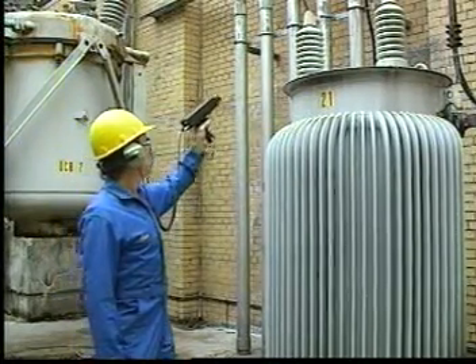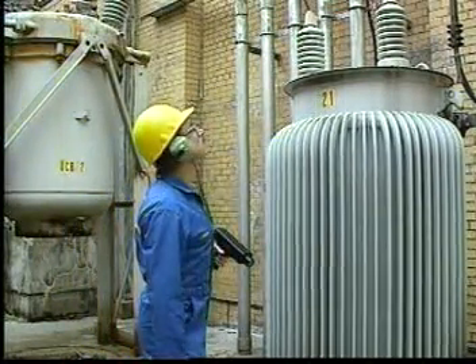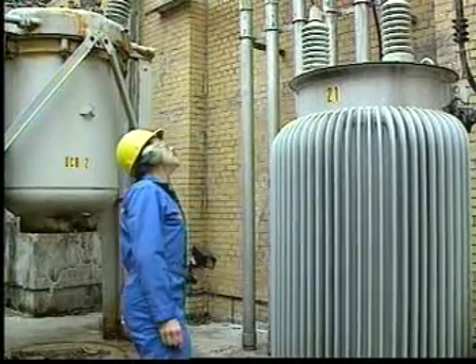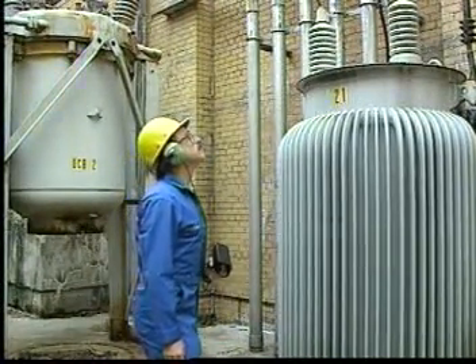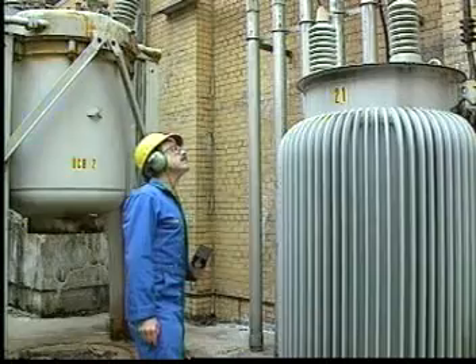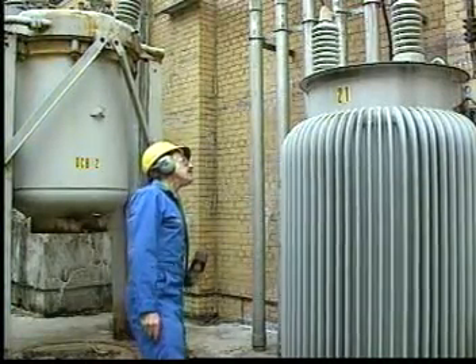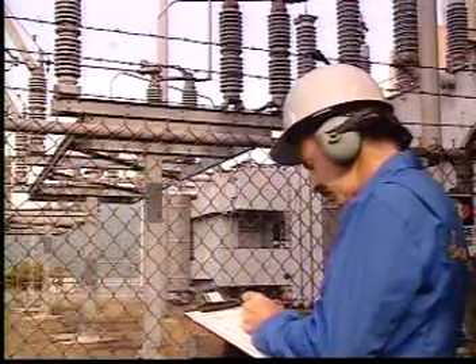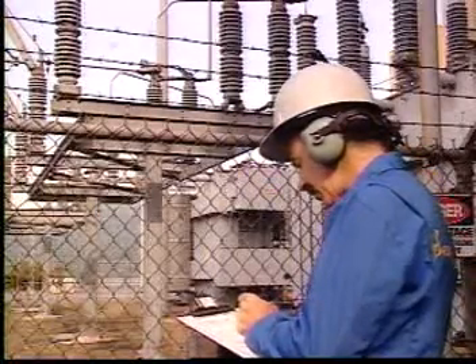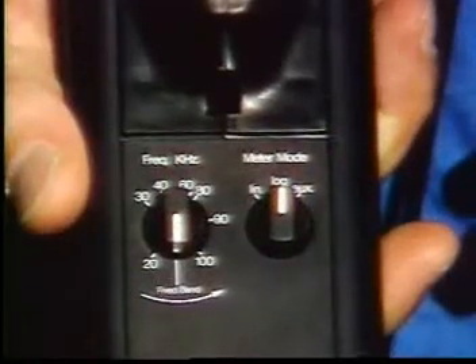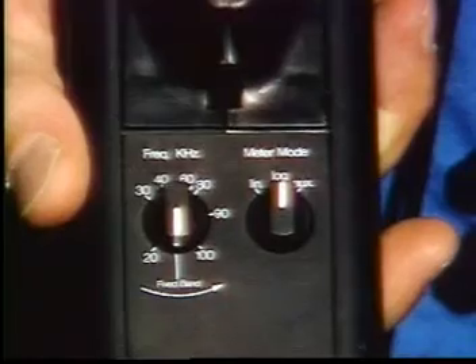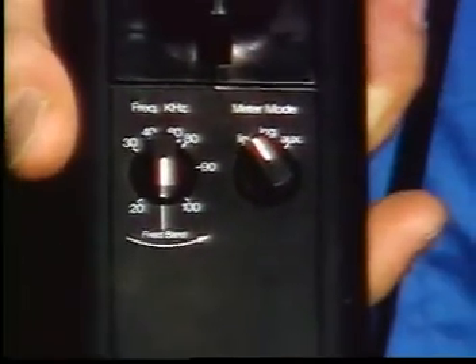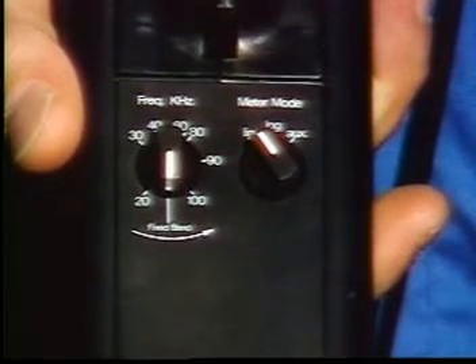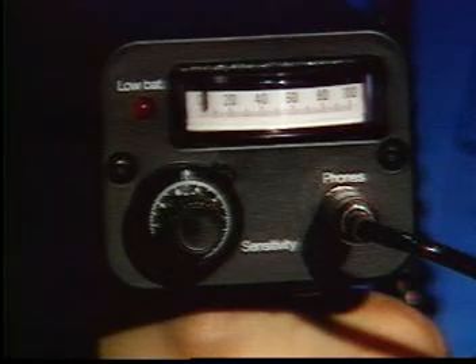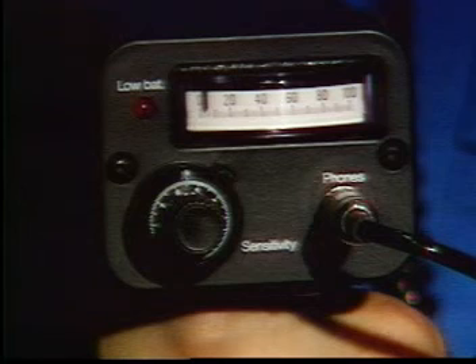Just as you may use complementary technologies, you may use your own senses to detect changes in your equipment. You may be able to smell ozone or see discoloration, for example. Monitor your equipment regularly by listening to everything and record the results. Although the log mode is used to record in real time when scanning to pinpoint a problem site, we recommend switching to the LIN mode for a steady response for monitoring purposes. This will also allow for noting decibel differences.